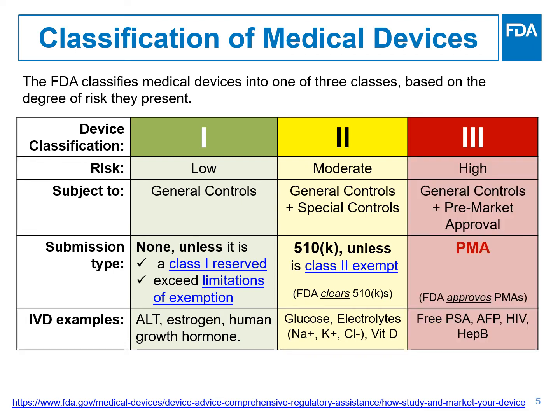Finally, the FDA classifies into Class 3 devices intended to be used in supporting or sustaining human life or preventing impairment of human health, or that may present a potential unreasonable risk of illness or injury, for which general controls and special controls are insufficient to provide reasonable assurance of the safety and effectiveness of a device.